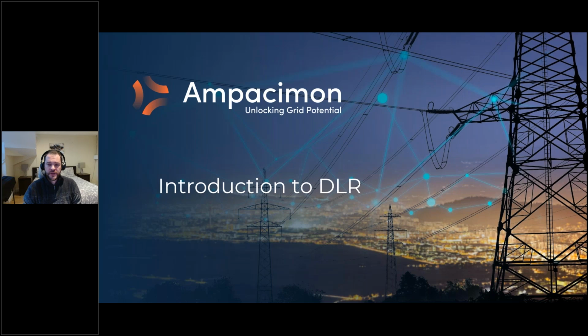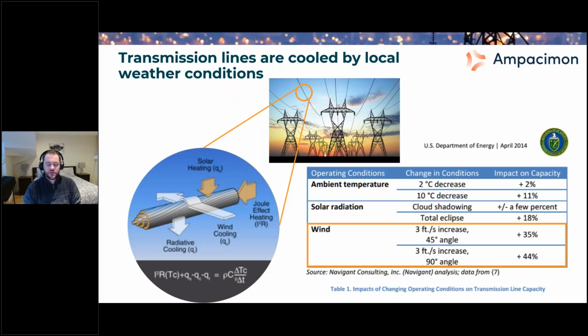So let's talk a little bit about DLR. DLR in essence is the idea of when you have an overhead line, you have a piece of metal in the air, and that piece of metal has two heat sources and two heat sinks, in simple terms. The heat sources are either solar heating, so heating from the sun, or heating from the current on the line. So the more current you push through the line, the hotter it's going to get.